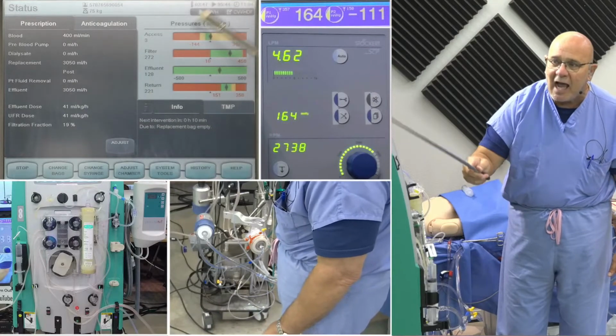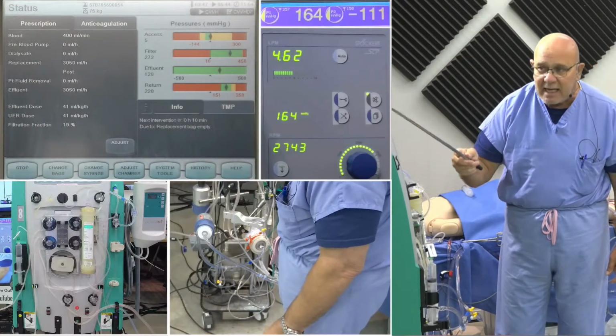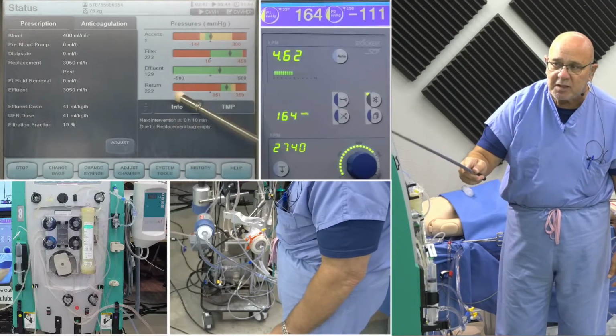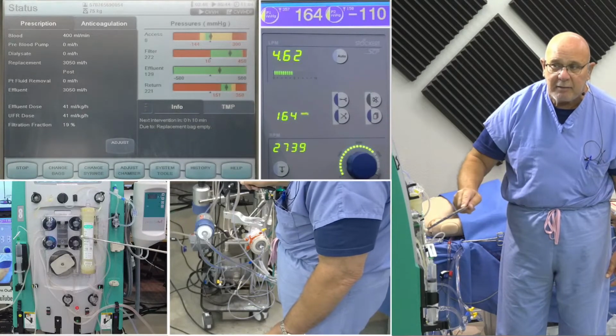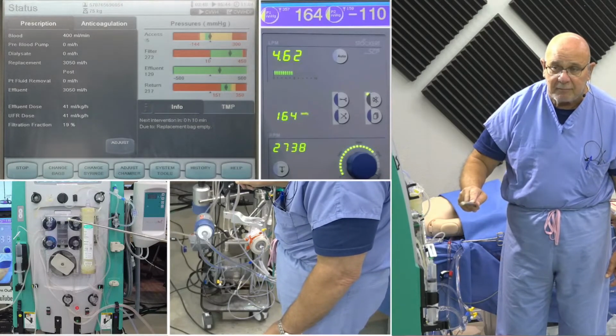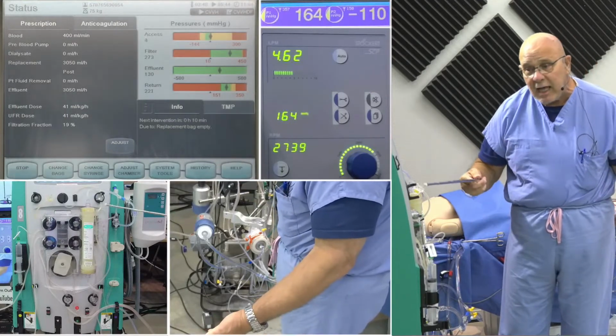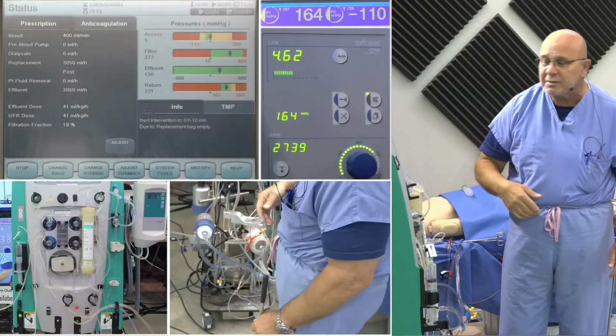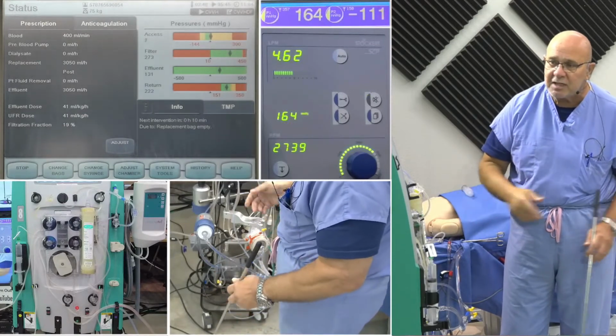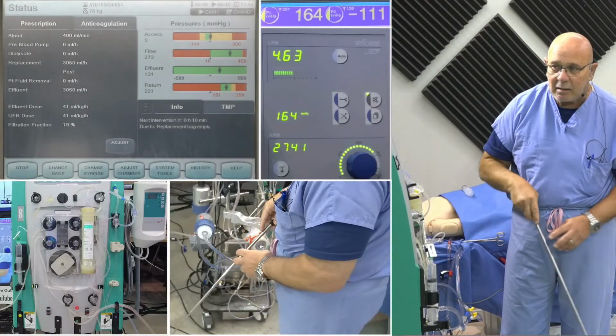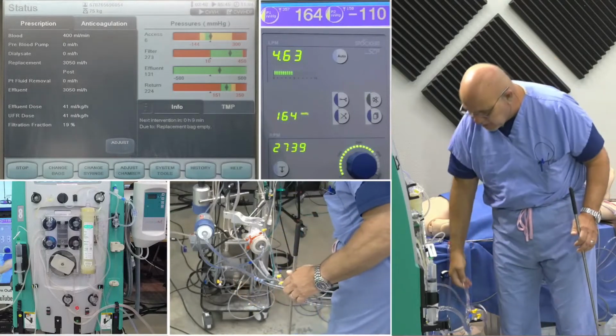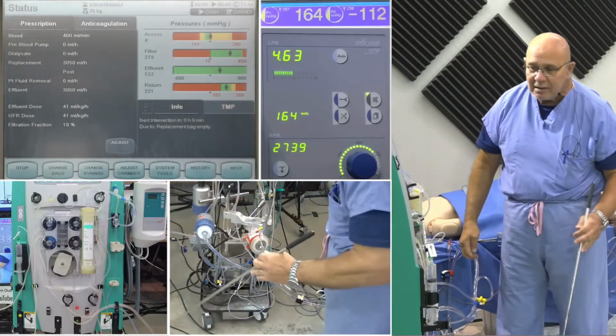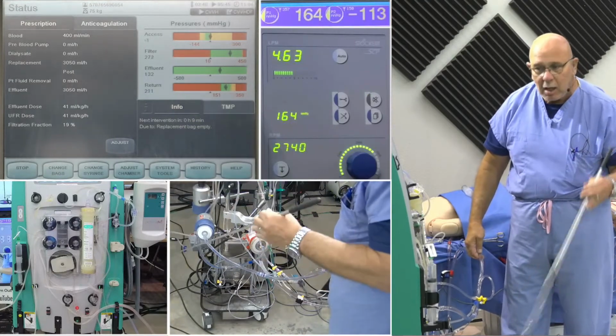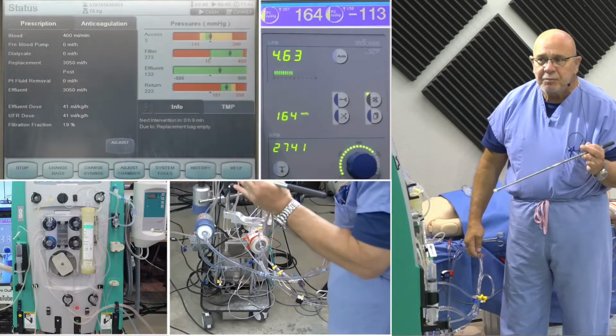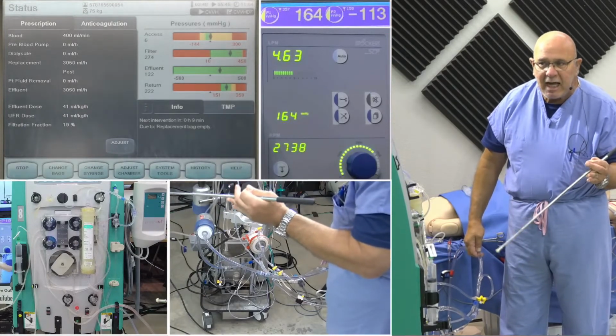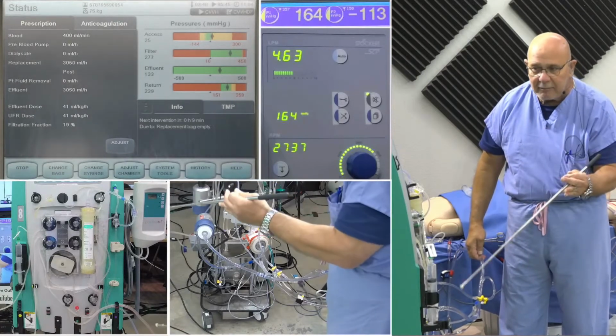This is going to give you hours and hours and hours, days, because the filters are good for 72 hours. This will give you a very long filter life, uninterrupted flow, and it's all going to work well. Now, caveat to that is if your patient is having volume problems and you're having to fluid resuscitate and do all of those kinds of things, might not be a good idea to have this there then, because if you have continuous interruption and these pressures change a lot, which I'll just demonstrate, you're going to get alarms. Alarms are a big hassle with these devices. They're very, very useful tools, but have pretty high sensitivity when it comes to varying pressures and flows.